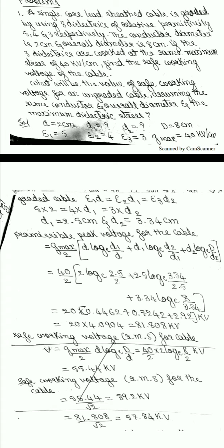Substitute the values, because you know the value of d1, d2 and capital D. Substitute all the values, so that you will get permissible peak voltage for the cable, 81.808 kV. Safe working voltage RMS for the cable, I have already said, it should be in peak value, it should not be in the RMS value. So 81.808 divided by square root of 2, you will get 57.84 kV, since they have asked for RMS. Okay, thank you.